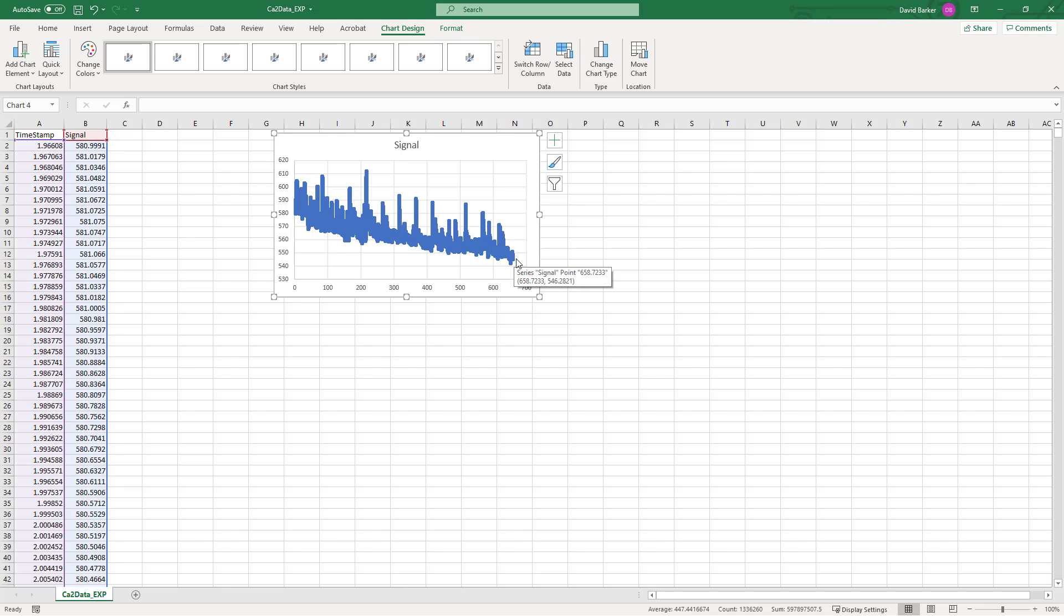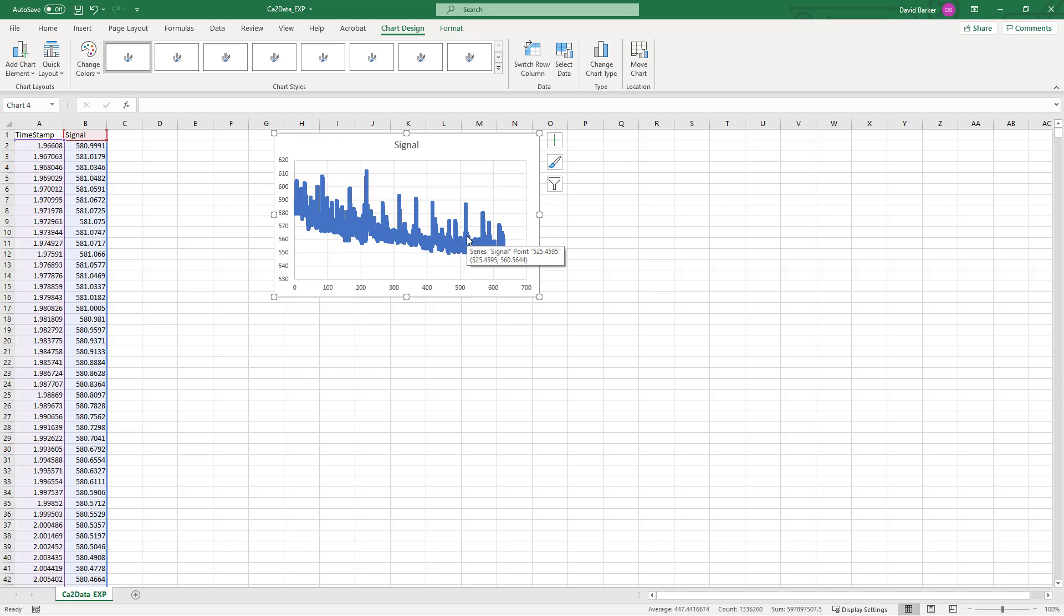Generally this kind of drift in the data is caused by photobleaching, and there are a number of different sources that have been theorized to contribute to this. The most likely case is bleaching of the tissue that you're recording from, but it's also been suggested that the fiber optics that you're recording through, especially if you're using long cables, might also have some bleaching of their photo signals. There may also be some changes in things like the LEDs as they warm up over time.